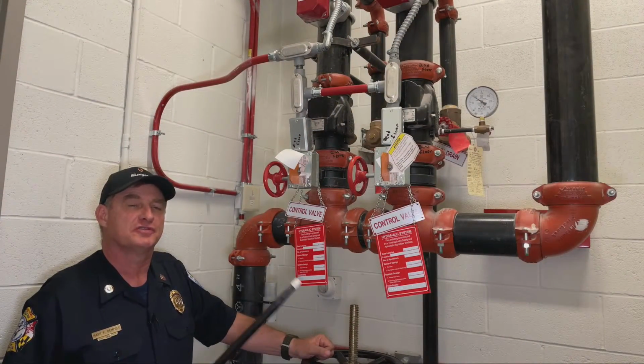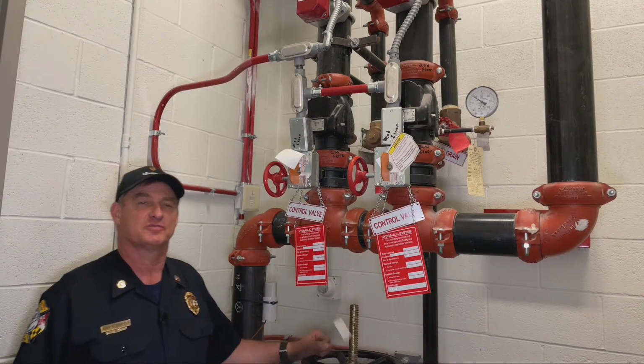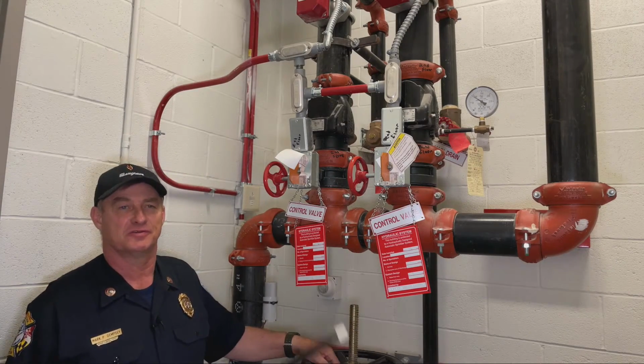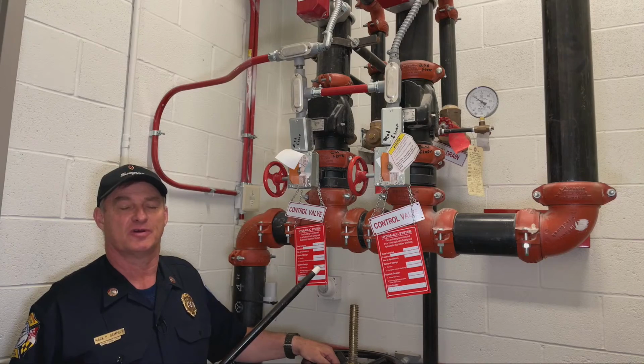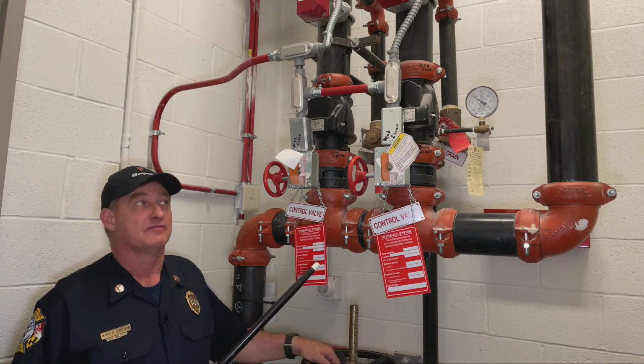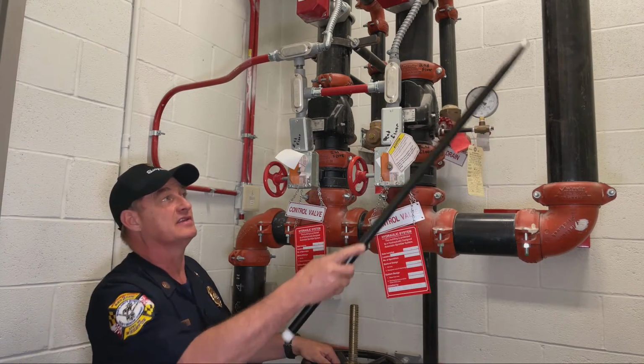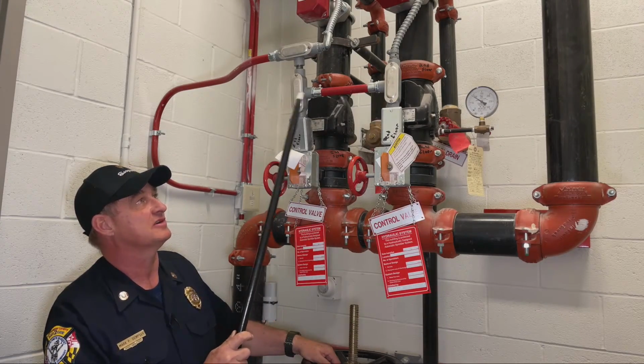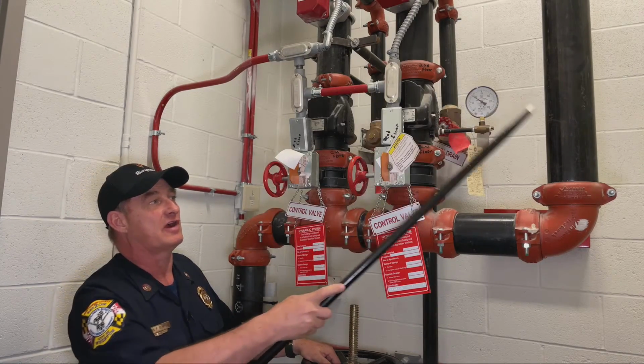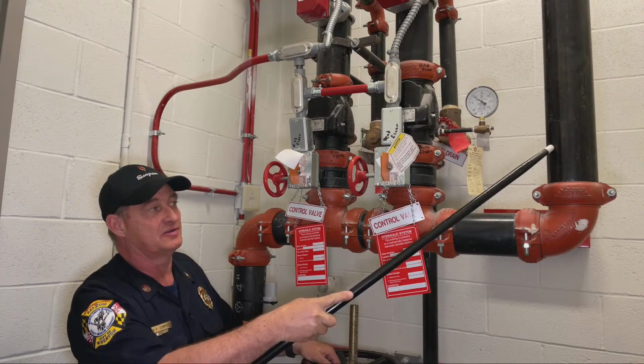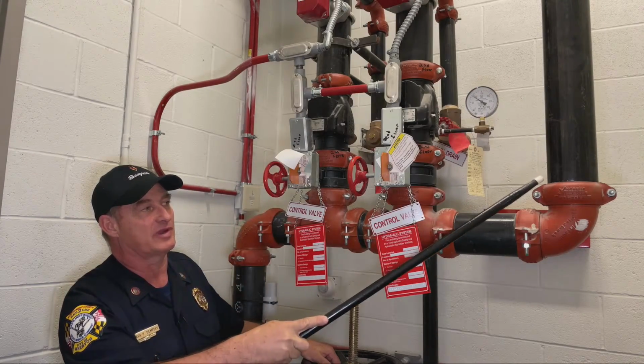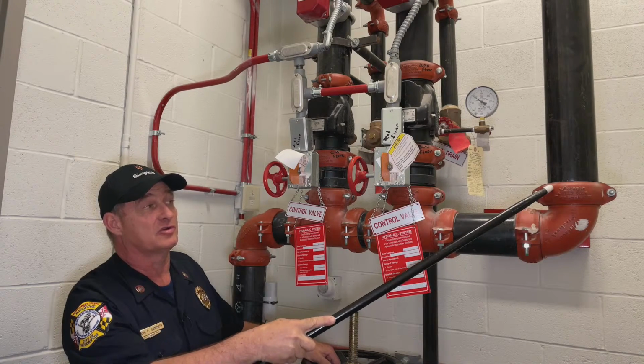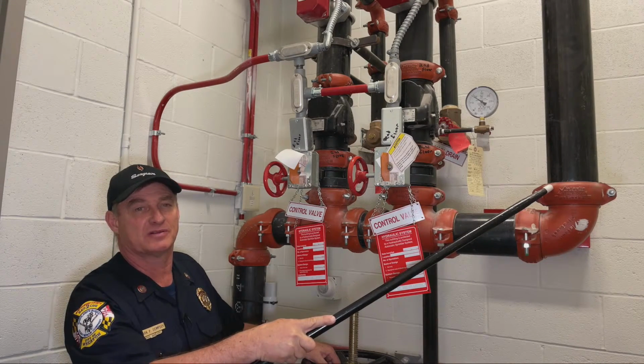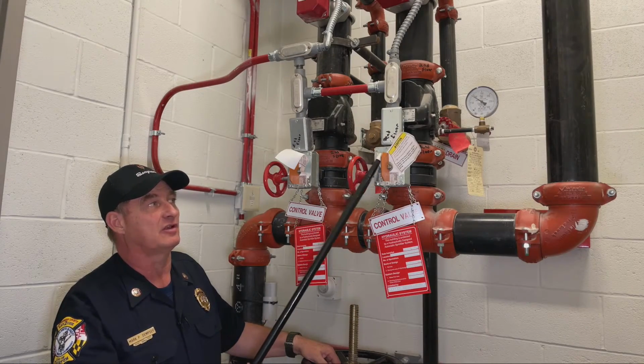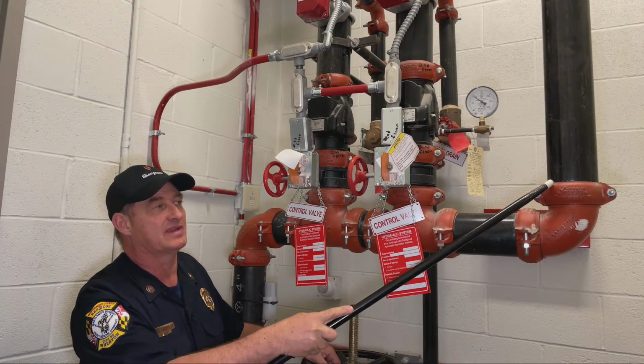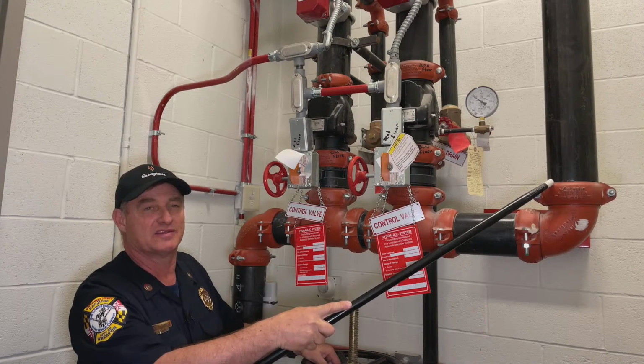All right, so 2/3 of all failures of sprinkler systems to control fires are due to valves being turned off that shouldn't be turned off. The fire department connection is designed in this system. It's a multi-zone system because we have a 2-story building. The fire department connection ties in here. You'll note there is no valve on the fire department connection line. So there could be an opportunity to visit the sprinkler room, find a valve closed, open it, and you're pumping into the FDC, would supply the system.